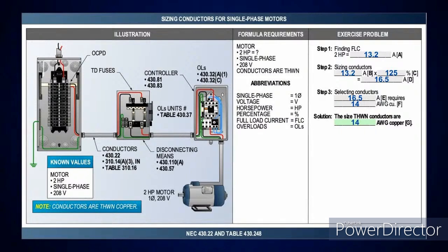Now, this one we looked at last week, and this is where we would look at sizing for a single motor. In this case, we're doing a 2 horsepower single phase 208 volt. In order to get the amperage rating, I brought this up the other day. If you look at 430.6(A)(1), it tells you anytime you're sizing the conductors or overcurrent protection device to use the amperages that are in the tables, 430.247 to 250. In this case, since it's single phase, we'll be looking at table 430.248.